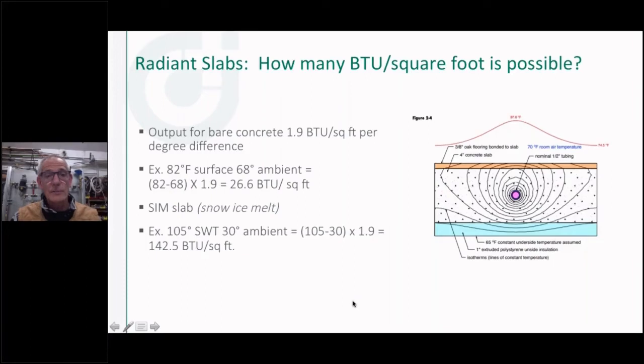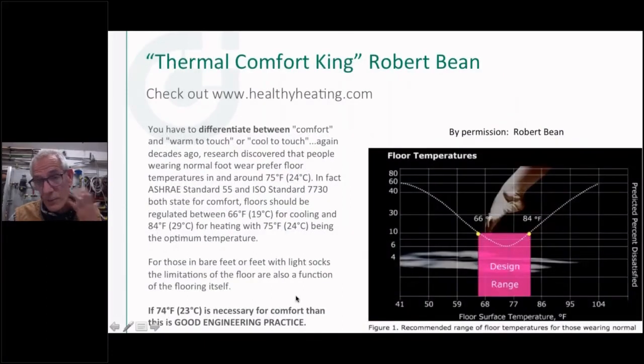So let's take that number and just do a little snow melt here. Let's say we're supplying a 105 degree supply temperature to a slab that's in a 30 degree ambient. Well, 105 minus 30 times 1.9, that's where we get such a massive output on a radiant slab that's outside as a snow melt instead of inside. I've got this big delta T that I'm leveraging from my supply water temperature to my ambient temperature. So that's how a square foot of concrete can give you so much different output.